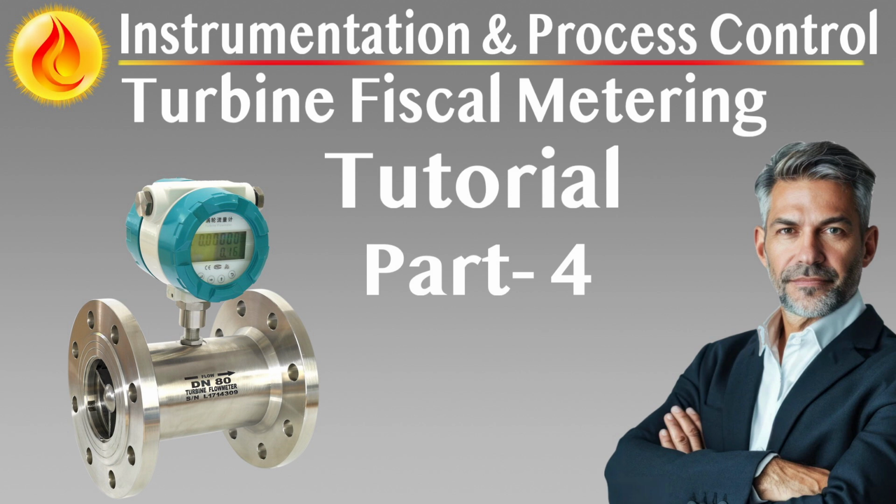The microcomputer must support manual or automated entry of the meter K factor, pulses per volume unit. This factor is applied in calculating gross volume flow, which is then compensated using live pressure, temperature, and density inputs to determine mass flow and standard volume at reference conditions, e.g. 15 degrees Celsius and 101.325 kilopascal.